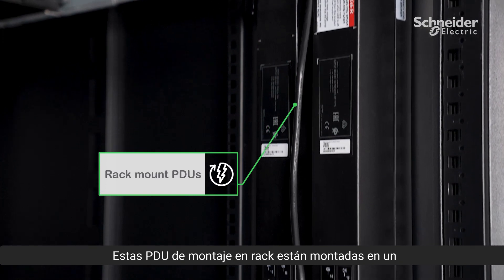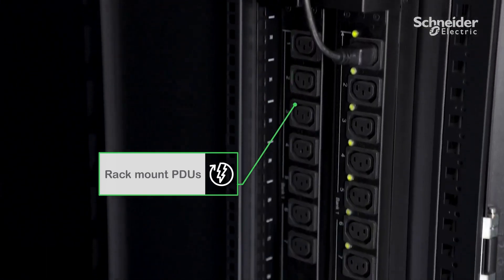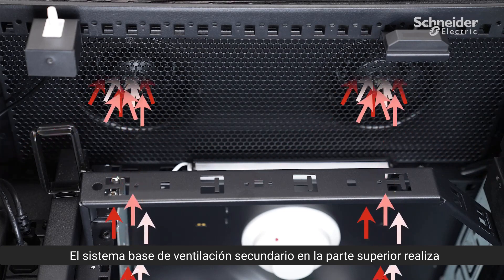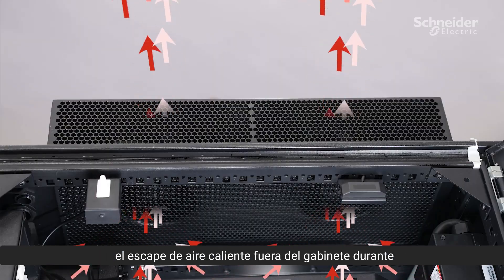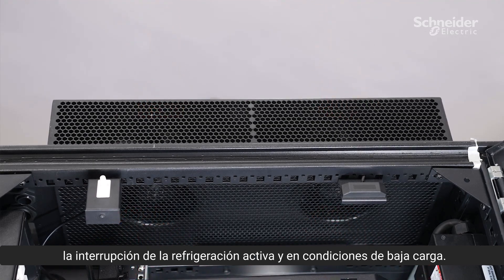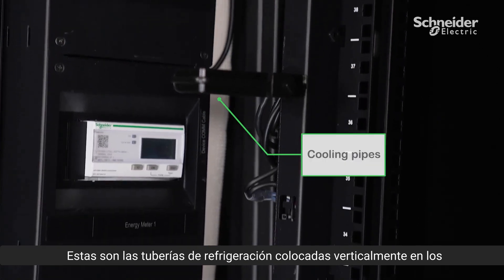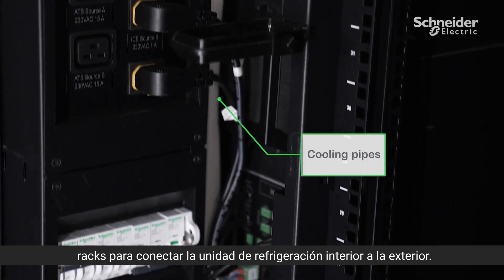These rack-mount PDUs are mounted in zero-U to power the IT equipment. The secondary fan-based system at the top performs the exhaust of hot air outside the cabinet during active cooling interruption and in low-load conditions. These are the cooling pipes routed vertically in the rack to connect the IDU to the ODU cooling unit.